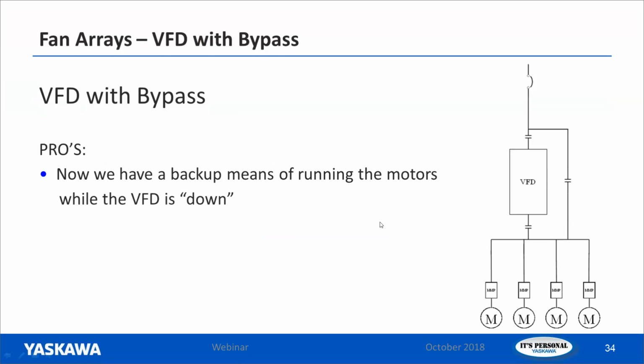Over here on the right, we have just that. Depicted here, we've got a drive. In this case, it's a 3-contactor bypass, circuit breaker upstream here, and we've got a 4-motor array with MMPs. So now we have a backup means of running the motors when the VFD is down. This right here would be the bypass contactor.